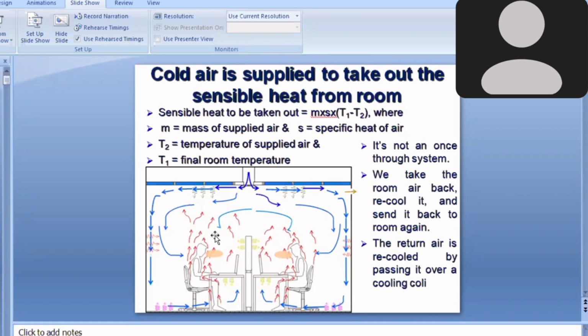So the sensible heat being taken out is equal to mass into specific heat of air into T1 minus T2. Mass is the mass of the air which is being supplied here. This is the specific heat of the air which is being supplied here. T2 is the temperature of the supplied air, which is less, and it's getting heated up, and T1 is the final room temperature, which is equal to the temperature of the air which is leaving the room.